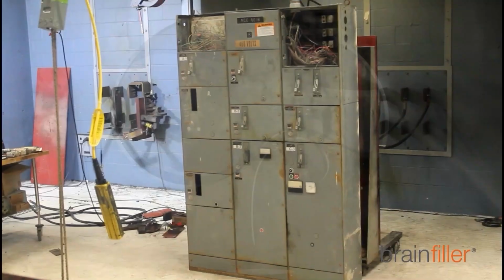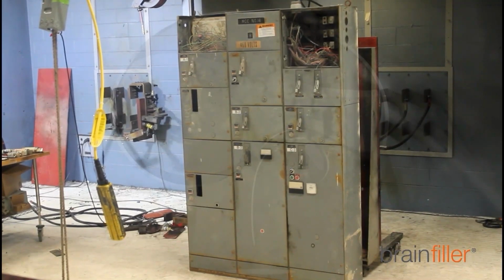So I have one more to show you, of a motor control center. Okay, test 27, door closed. 2, 1. So much for the door being closed. I have a keen perception of the obvious with both of those. The doors aren't going to offer protection. It's like, well, yeah. I was just illustrating that sometimes the doors will blow open and you just don't know. So that's what was behind this note that was added to NFPA 70E.